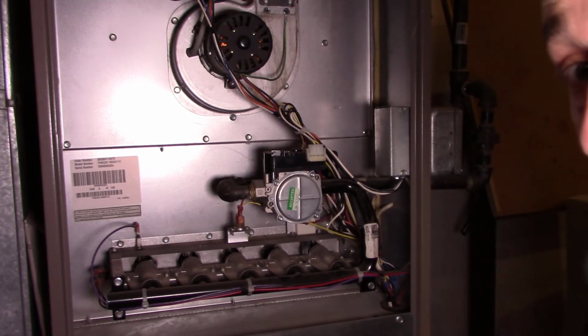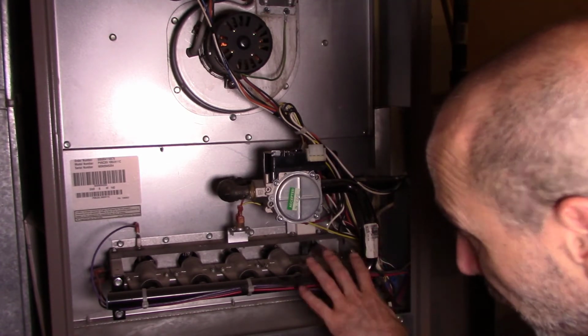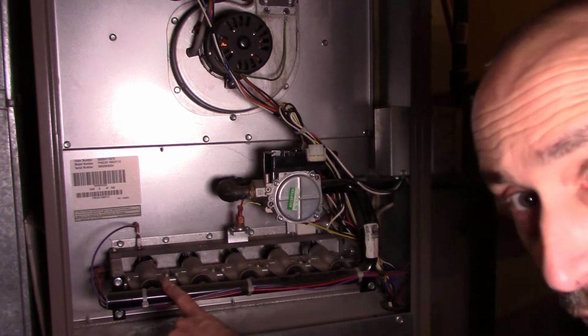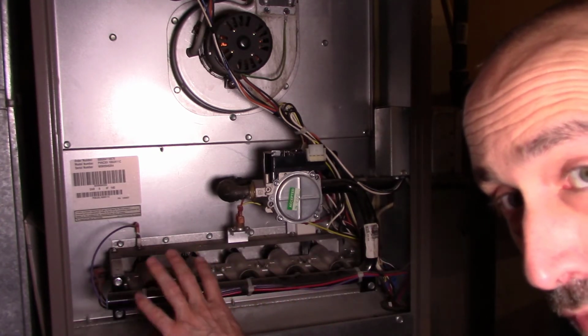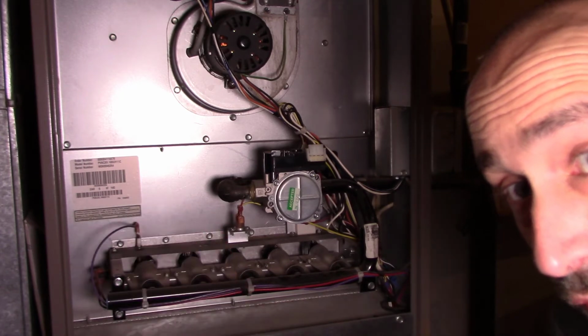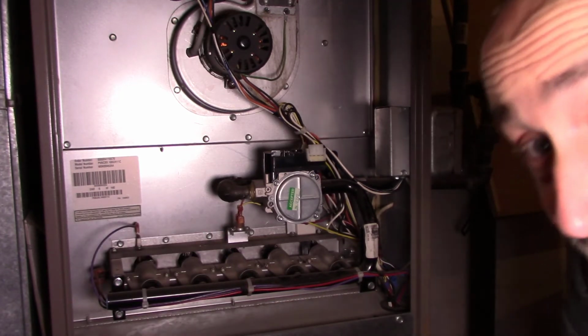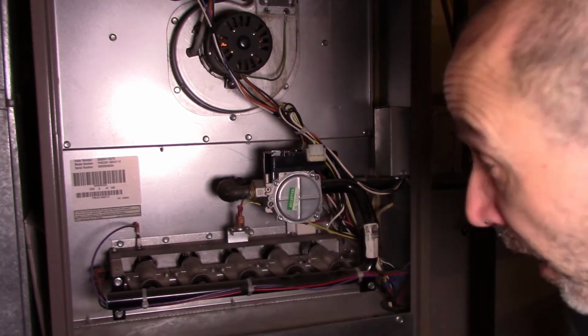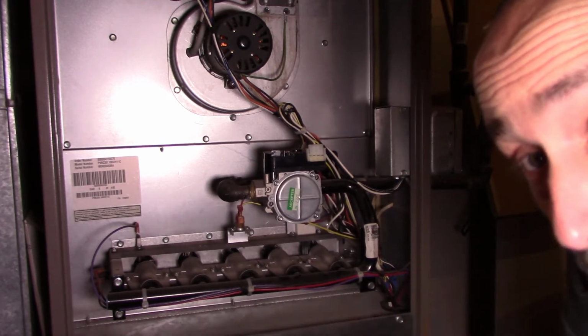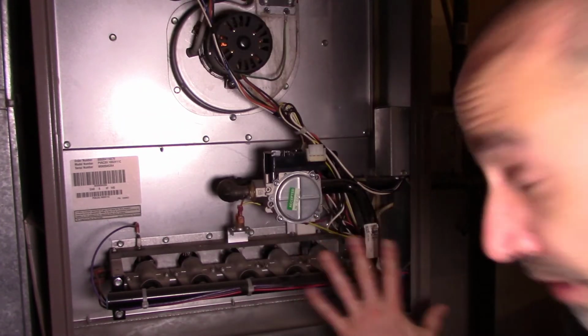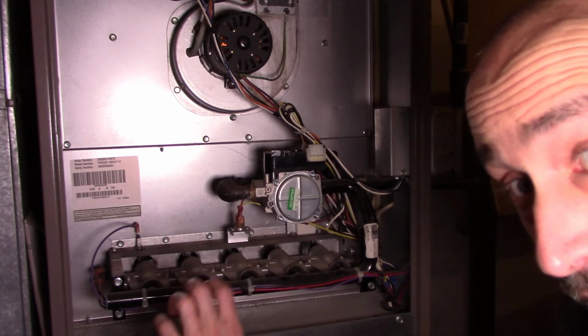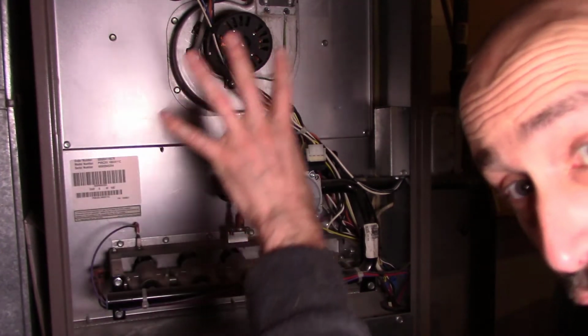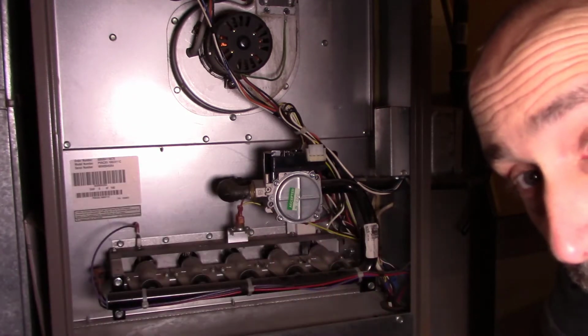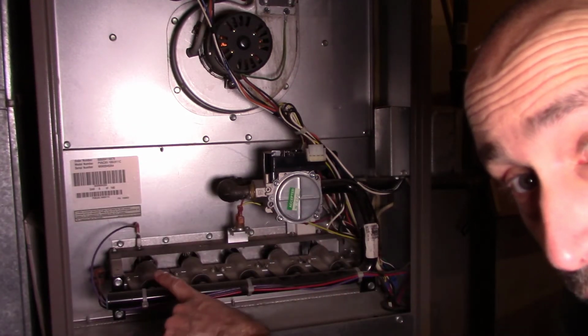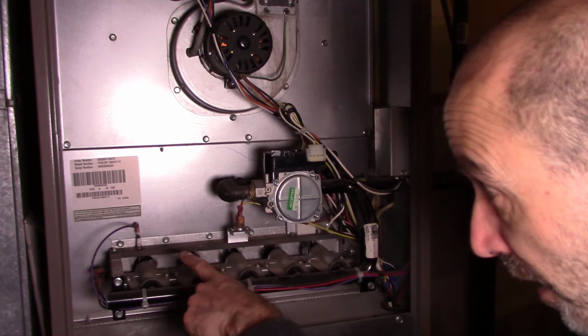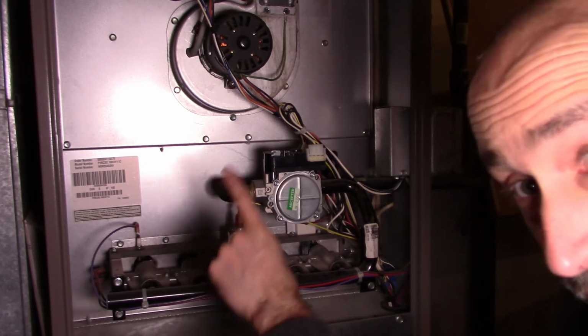Now, let's say you get ignition, it spreads across all the burners, but then after a couple of seconds, everything just shuts off. This is a very common problem, and it has happened to me on this furnace as well. It's one of the most common problems of any furnace: everything starts up, all the ignition fires, and then after about 2 or 3 seconds, everything shuts down for no reason. That's usually the flame sensor. The flame sensor is either dirty or it's bad, and that's a common maintenance problem.